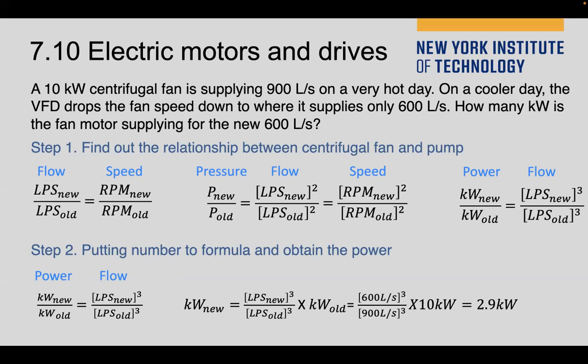Assume we're on a very hot day. On a hot day you need a strong fan to keep cool, so you have a 10 kilowatt centrifugal fan supplying a high flow rate of 900 liters per second. In summer, on a hot day, you need that large flow rate to keep your body cool. But on a cool day you don't need as much, though you still need some fresh air. So if we install a motor that can adjust the speed, a variable frequency drive, the speed is adjustable, and we only need 600 liters per second, that's fine.